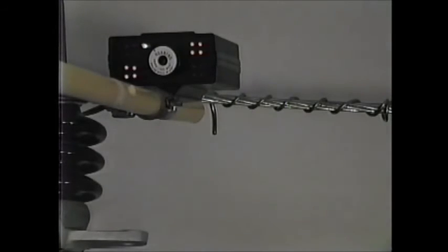Again at the same voltage level, now instead of having the three lights we expect, we're picking up four banks of lights. The reason for this is the unit is installed very close to an insulator that has a grounded base.